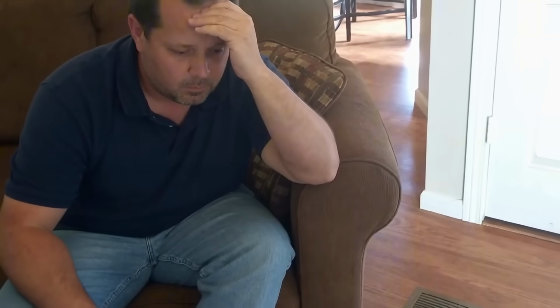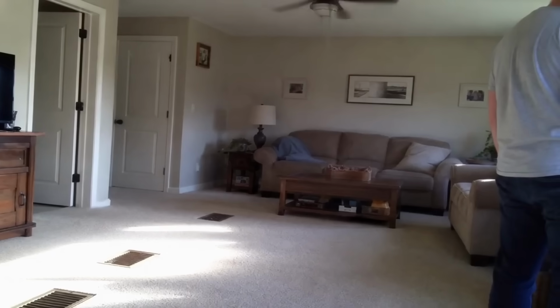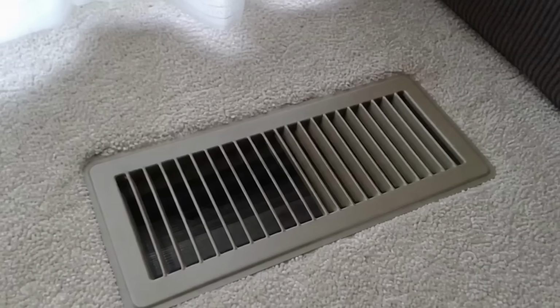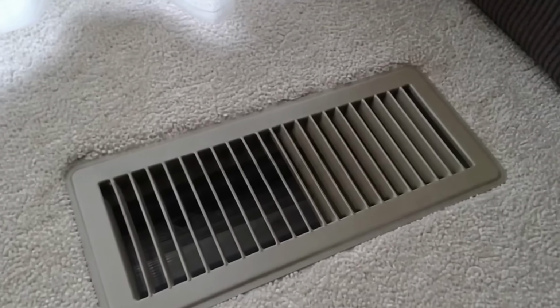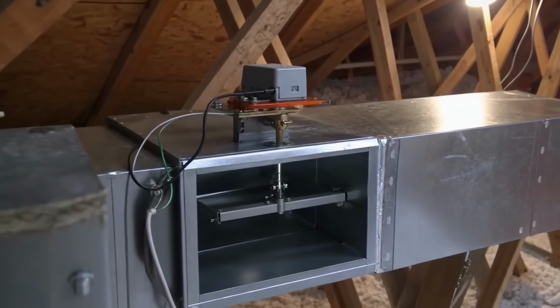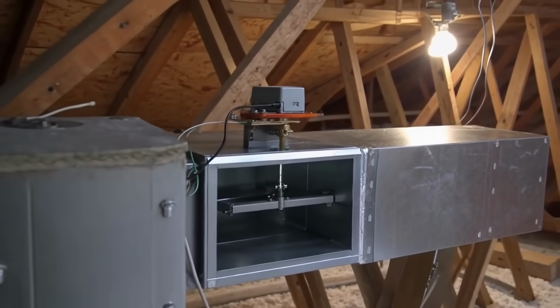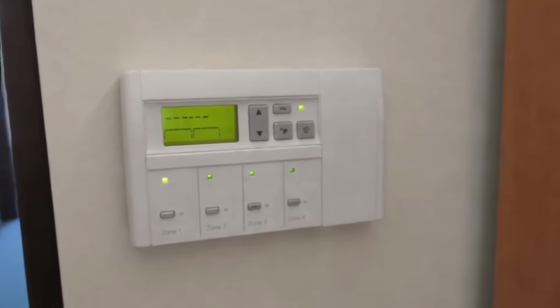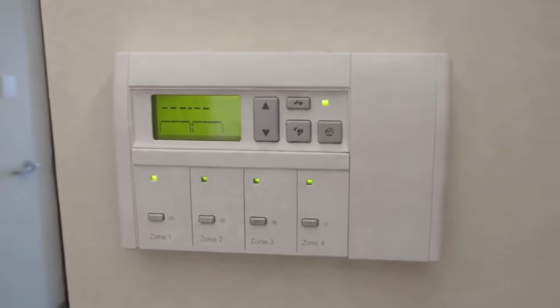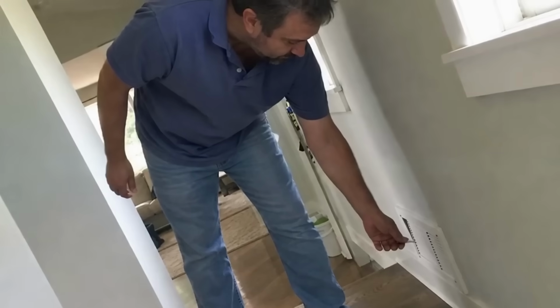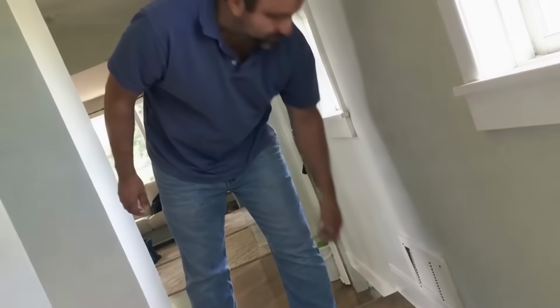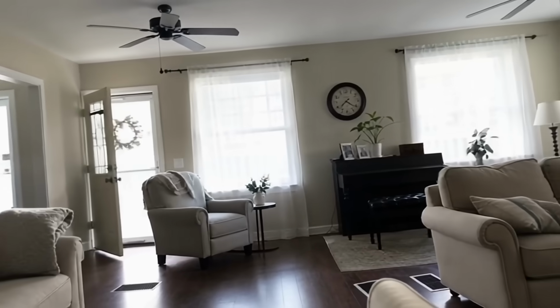You didn't save a dime. You strained the motor, iced the coil, and leaked more cooled air through cracked seams than that closed louver ever held back. So leave them open, all of them. Real zoning, cooling one part of the house and not another, is a genuine thing. But it takes motorized dampers built into the ductwork and a control system to run them. It is not something you do by flicking a lever with your thumb. Open the vents and let the system breathe the way it was designed to.